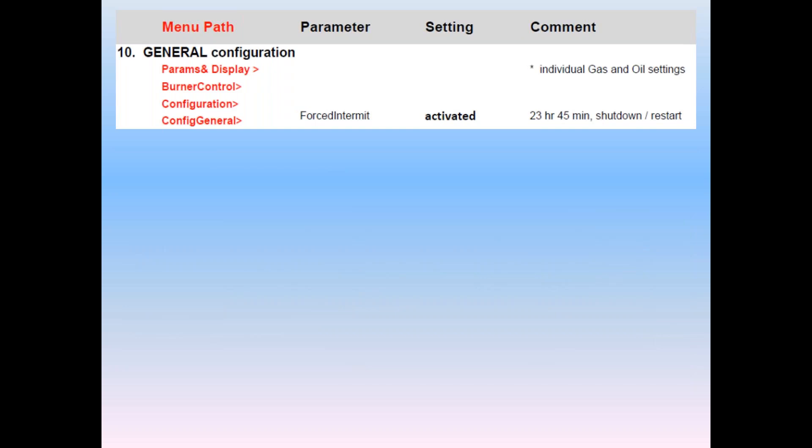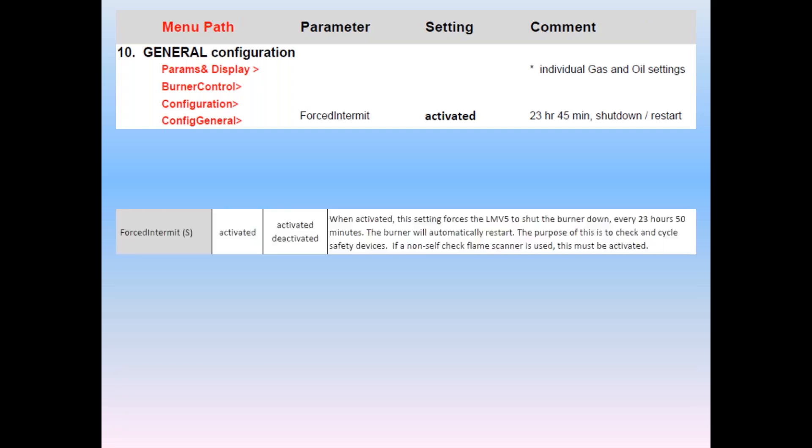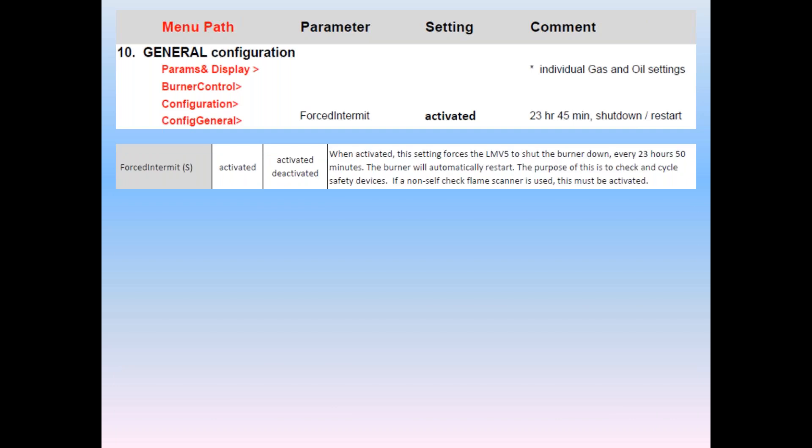If a unit is used for process loads, a call for heat can occur quite quickly. Well before the post purge even finishes. Option then is to select direct start. Result is load is satisfied. Unit enters the post purge, for which it has two parts. Mandatory, say two seconds, and optional, say 28 seconds. No quick call for heat would result in a 30 second purge, the mandatory and the optional. If there was a call for heat, after two seconds of mandatory post purge, it would skip the optional post purge and drive directly into pre purge and sequence back on. Biggest time saver is the shortening the post purge and the air actuator remains open. And that saves minutes driving closed, only to reopen for post purge as soon as it gets there. This is a quick for turnaround time. This feature requires a three-way solenoid on the air switch to test the air switch, even though the fan never stops running. Forced intermittent, if activated, will cause the burner to cycle off and then cycle back on whenever 23 hours and 45 minutes of continuous operation occurs. This is often a code requirement to check the scanner operation.